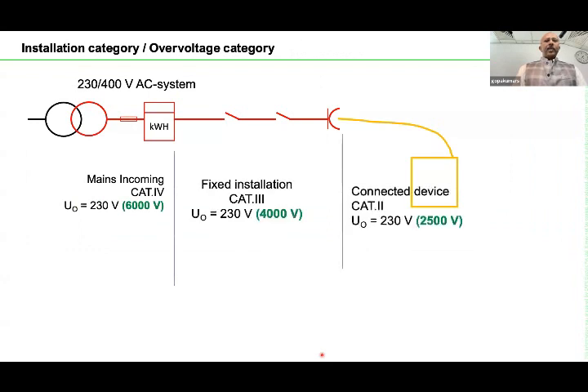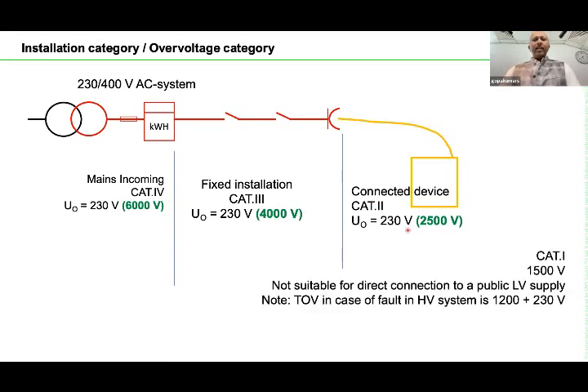Then you should also look at where these devices are installed in your building. According to the recommendation of the standard, every electrical apparatus at the main distribution board must be of category 4, the fixed part of the installation category 3, connected portable appliances category 2, and then the category 1 device.